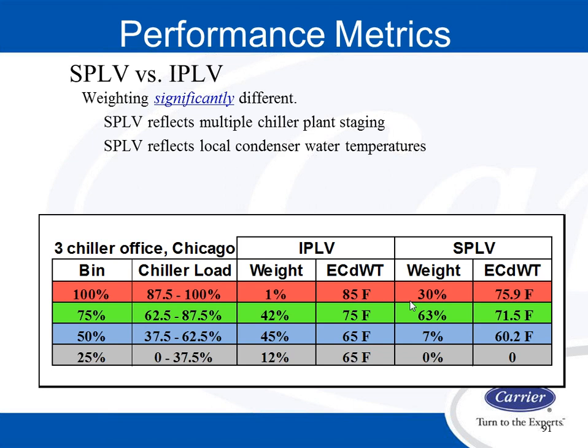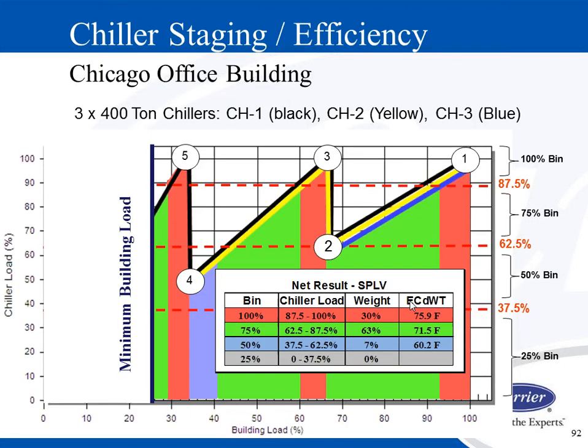So when we analyze and compare the IPLV versus the SPLV, again, the 100% load point, we said, happens 1% of the time with 85-degree tower, where it actually happens when you analyze the building 30% of the time with 75.9 degree entering condenser water temperature. The 75% load point in IPLV said 42 was 75. It's actually 63 with 71.5. And the 50% load point used to be 45, 65, and we're at 7%, 60.2, and the 25% load point never happens in our system part load analysis. And this is a typical Chicago office building.